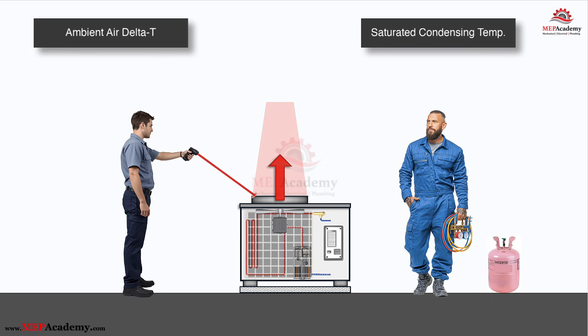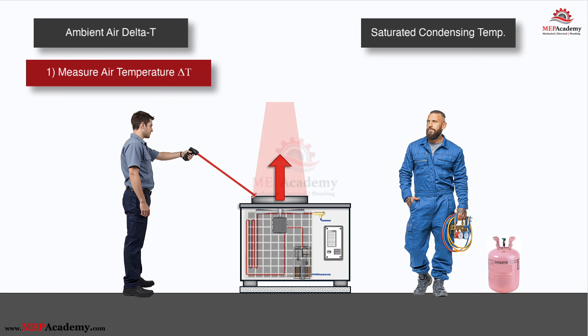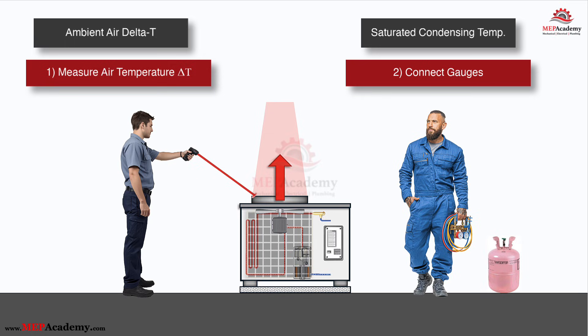Here's the rule I teach every tech on my crew. First 60 seconds at the condenser: always measure air delta T — it's that fast. If it's 10°F or 45°F, you instantly know you have a big problem. If air delta T is in the normal 20 to 30°F zone, stop and hook up gauges. Take the two extra minutes and calculate real condenser temperature difference — that's the only way to separate dirty coil from overcharge from non-condensibles from wrong ECM speed. Use the quick method as a screening tool. Use the real method to write the prescription. Stop feeling the forehead with an infrared gun and telling the customer their system is fine — take the real temperature. Air delta T is a clue. Condenser delta T is the diagnosis.